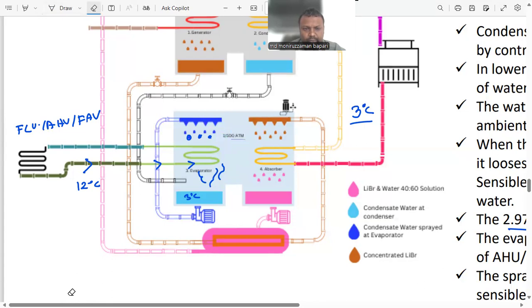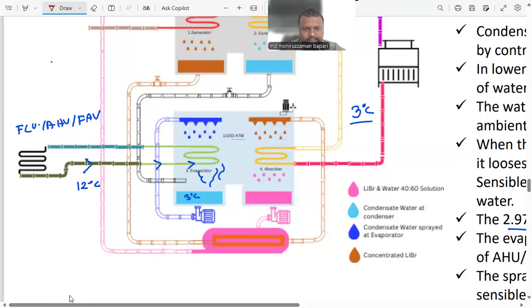Remember, for evaporation, again, we are going to need latent heat. The source of latent heat is the water inside this evaporator coil. And two things happen here. Firstly, the water which drips on this heat exchanger boils up and evaporates here. Evaporation happens. And secondly, the temperature of the water falls down to 6 degrees centigrade.